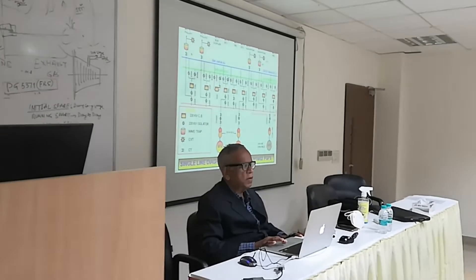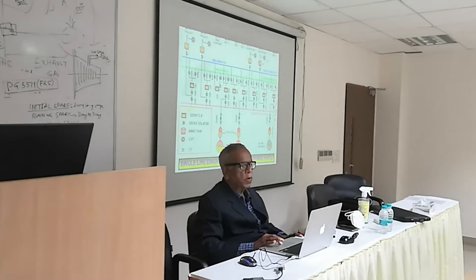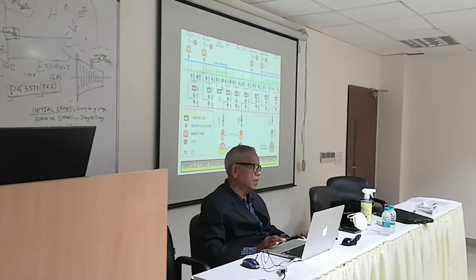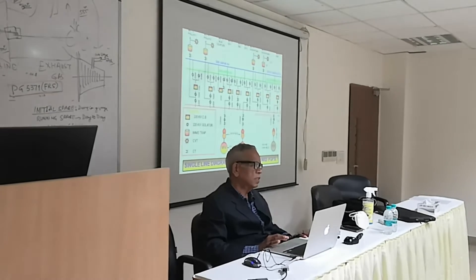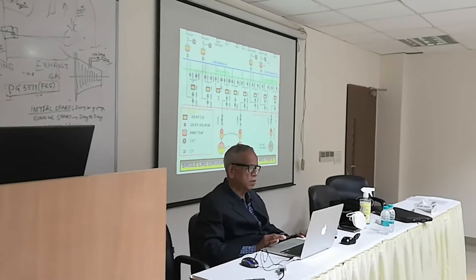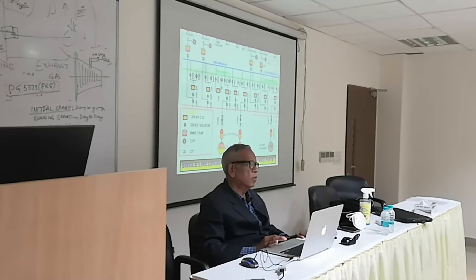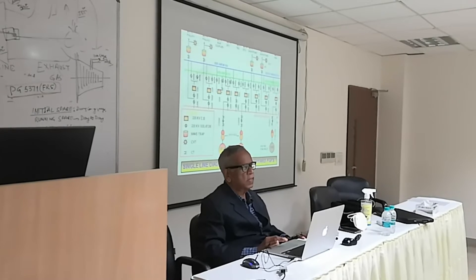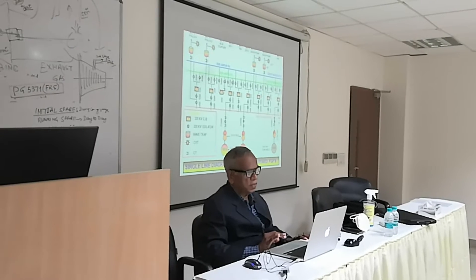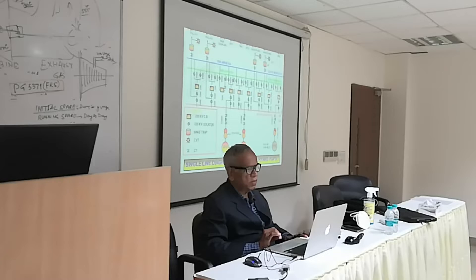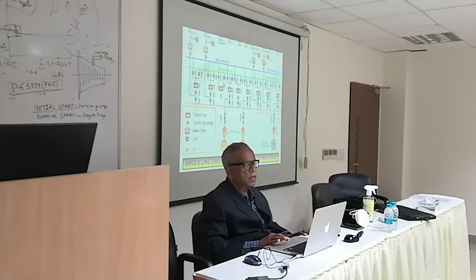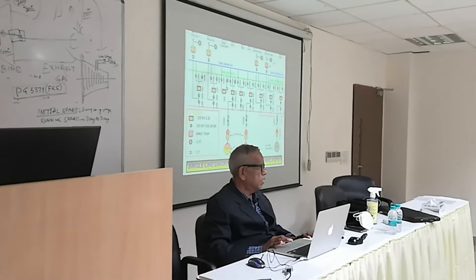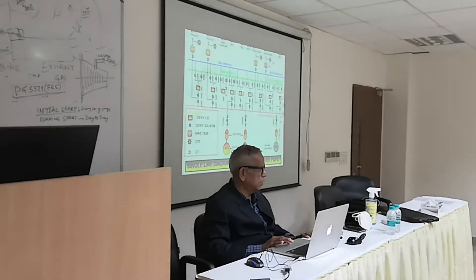Then there are wave traps. The purpose of a wave trap is to block the communication signal, because these high voltage substations can communicate with remote substations using the same transmission line over which power is flowing. The role of the wave trap is to stop the communication signal from entering into the substation.